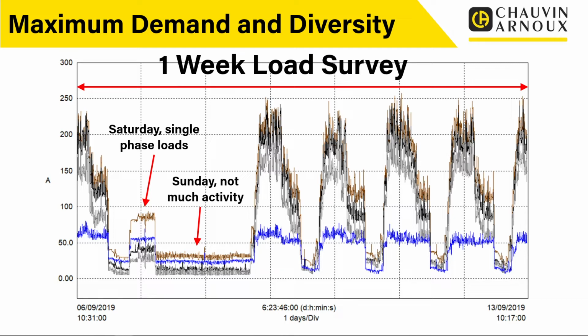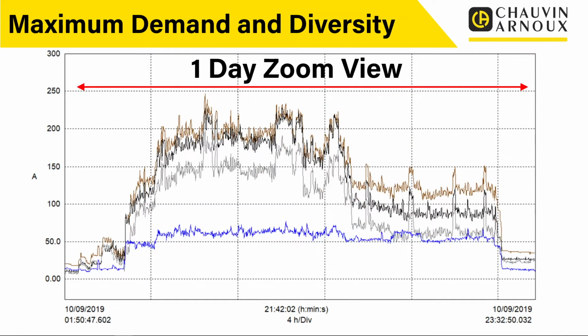But it may be a 300 amp supply, it may be bigger than that. So again, once we start looking at this, we're making some estimations, but it's based on real data, based on the actual figures we can see. And what we can do is take that a step further and zoom in to a 1 day view. We can continue to zoom in if we wanted to, and really get in on that data. So we can start to see what happens over the course of a day. Now, obviously, we're logging the whole installation here, and you could do this per circuit. You could even do this for particular items of equipment, but this is the whole installation in one go.